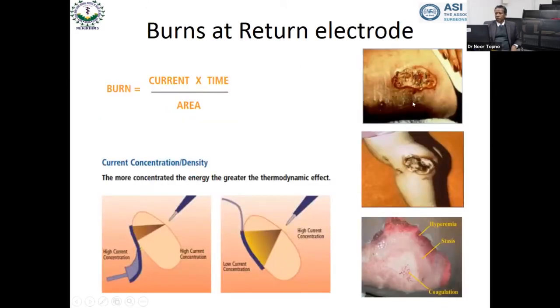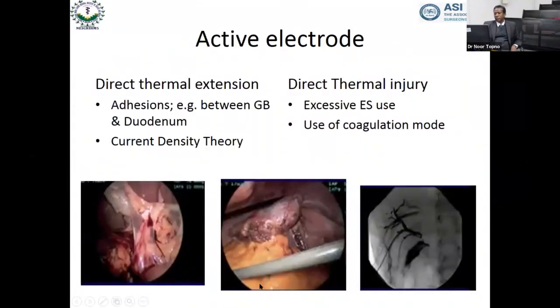This is just to show you the kind of burns you can get at the return electrode. That usually happens, like here, when the contact between the body surface and the electrode has come off. So the contact area has become much smaller. Therefore, the current density becomes much larger. And there is more generation of heat in that area, and that's how burns happen. As long as the contact is good, there is good dissipation of current, and usually a burn does not happen.